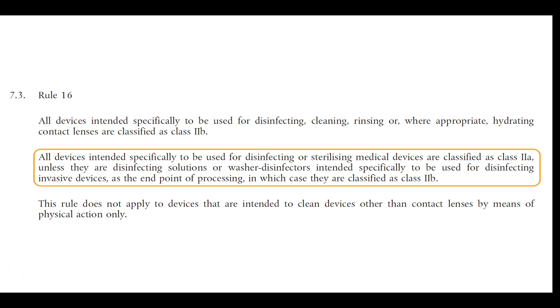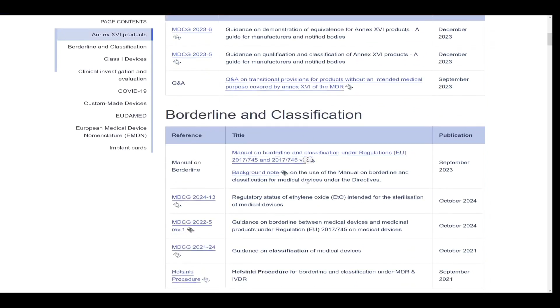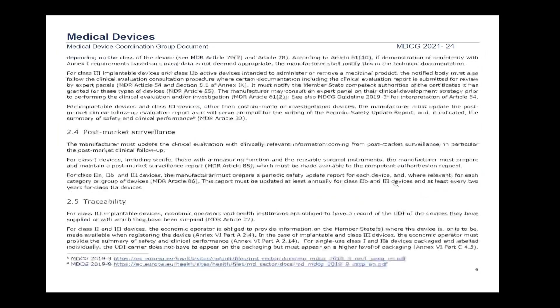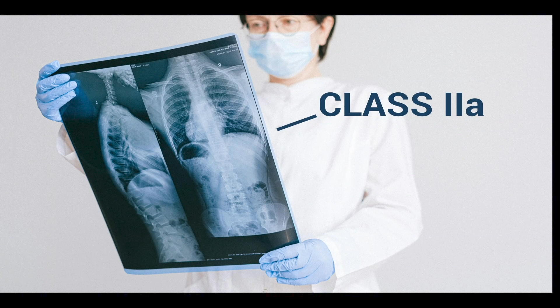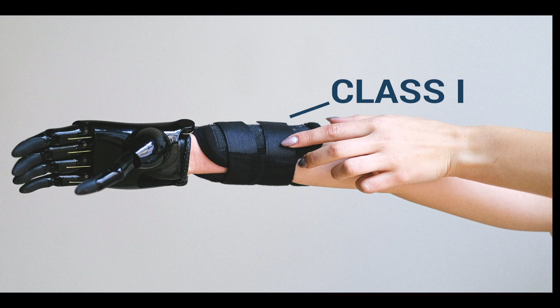There are quite a few more interesting rules in Section 7 that apply to all kinds of devices that you may not even have expected to be medical devices at all. Various examples are given in the EU guidance document on classification of medical devices, with many helpful explanations for each rule in MDR Annex 8. It explains why X-ray films are Class 2A medical devices under Rule 17, and that the leather straps for fixing a prosthesis are Class 1 devices according to Rule 18. And did you know that salt water being used as a nose spray is a Class 2A device because the mode of action of the salt water is physical and not metabolical, and hence it falls into Rule 21? Well, now you do.